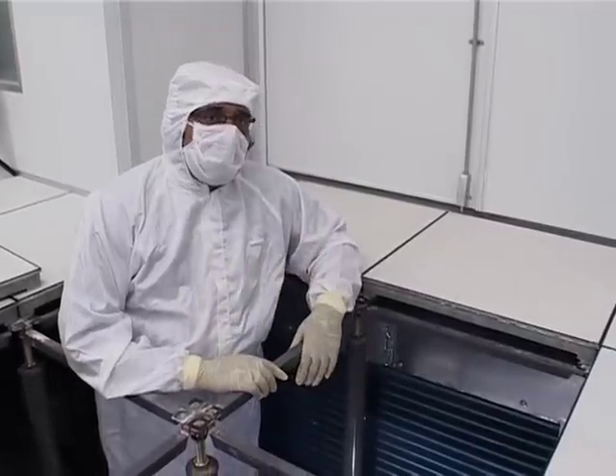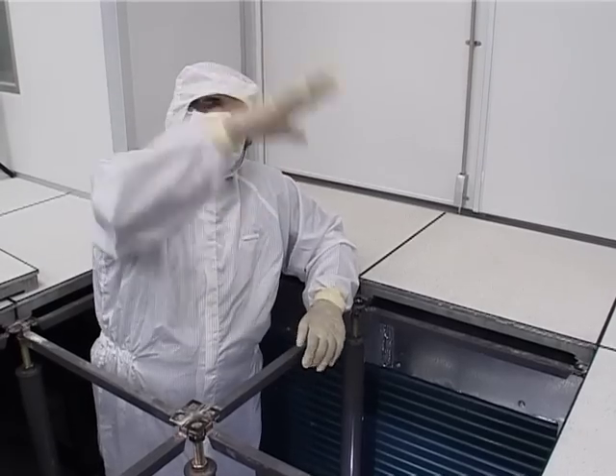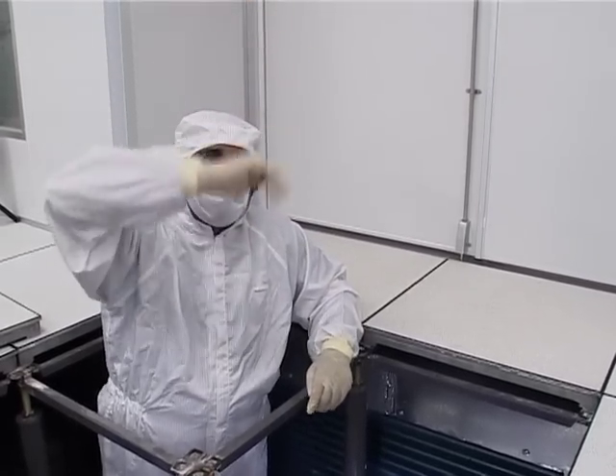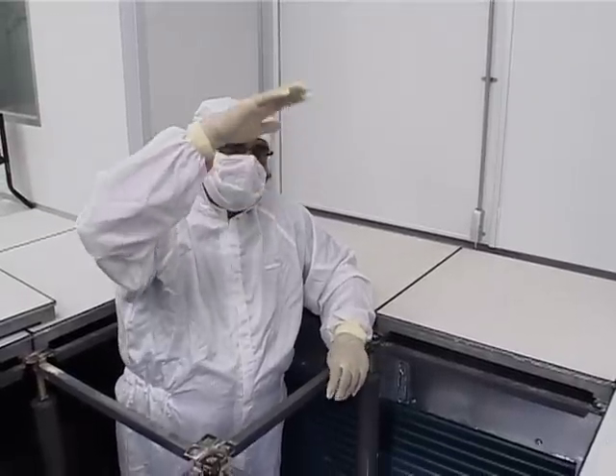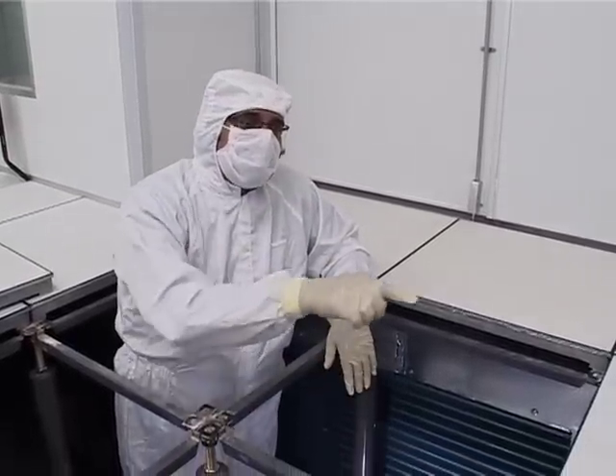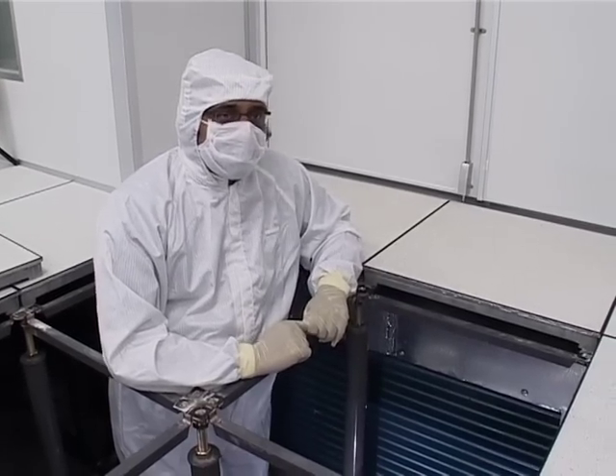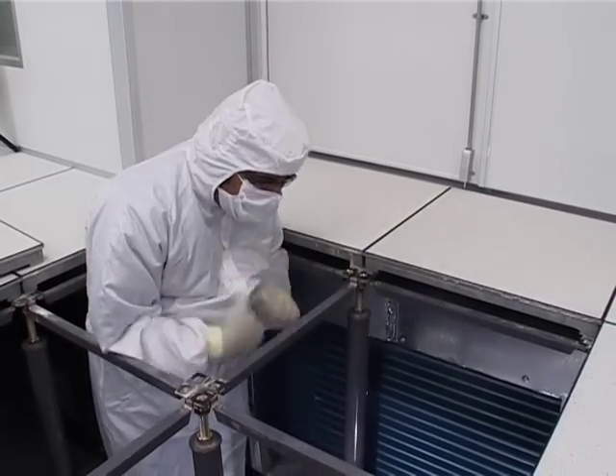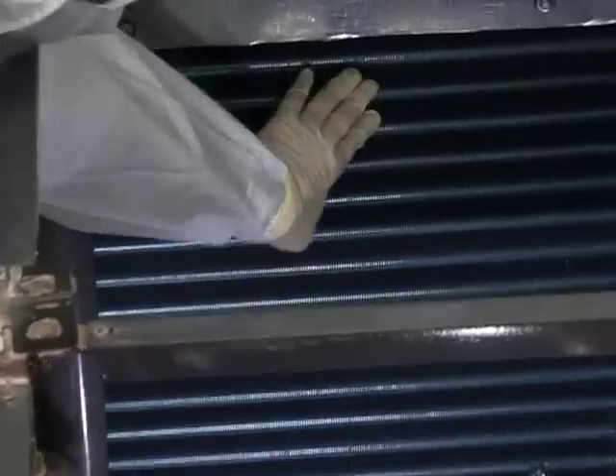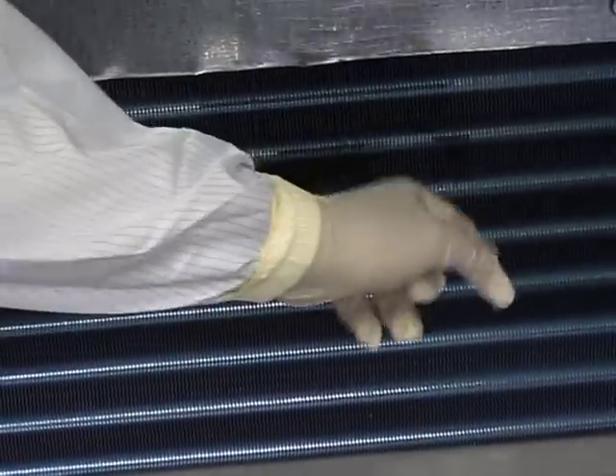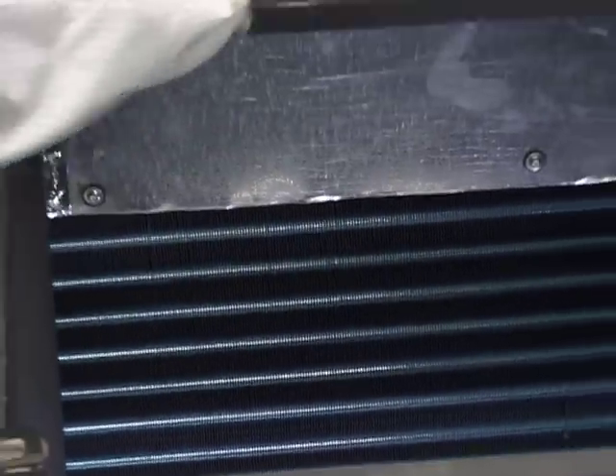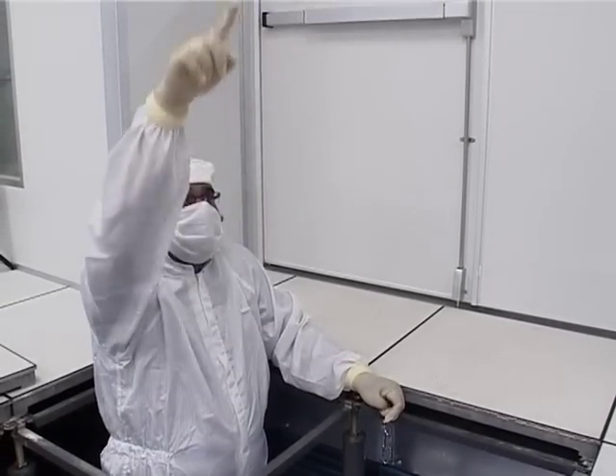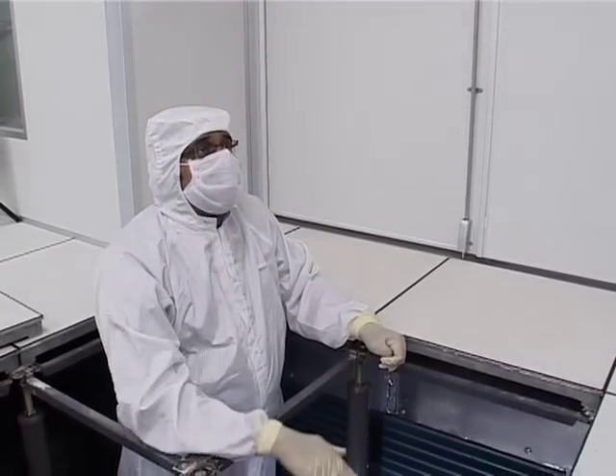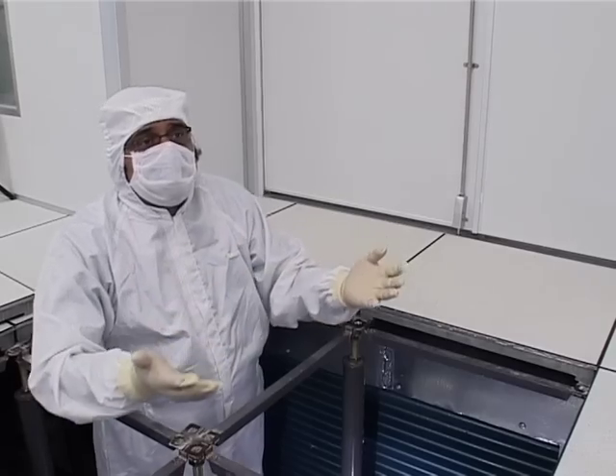I have explained to you earlier that the air enters this cleanroom through the fan filter units from the plenum. And the air that is in the cleanroom is taken to the subfab area through the perforated tiles at the floor. The air that comes into the subfab area, or the basement of this cleanroom, is passed through this kind of cooling coils. So the air after passing through this cooling coil is taken to the return air chase and it is brought back to the plenum of the clean room. And this process continues, and that maintains an airflow from the plenum to the subfab area and maintains cleanliness within the clean room.